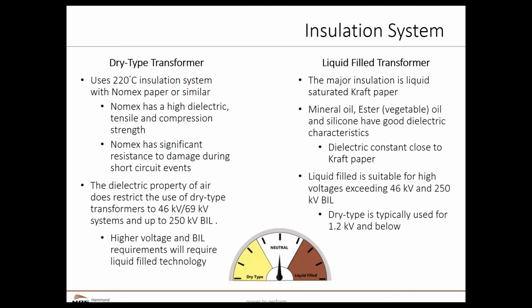So let's talk about insulation systems. With a dry type transformer, we generally use Nomex, and there are a couple other products that are similar to Nomex. But again, it's a very expensive, very high-tech, very effective way of insulating a transformer that will last decades. Nomex is very strong. It's what firefighters' big suits that are flame resistant are made out of. It has really good properties for both handling long-term heat and insulating. In addition, we also use air gaps.